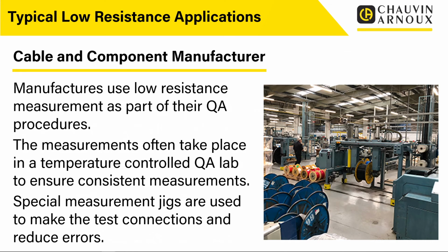They'll position the sample into that, clamp it down and take the measurements, and with that they can control the environment, control the measurements, reduce any errors as much as possible, and get a consistent measurement. So it's quite a common application for these sort of manufacturers to use micro-ohmmeters as part of their quality assurance procedures for their manufacturing processes.